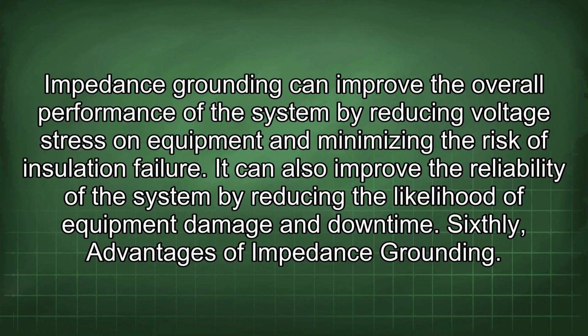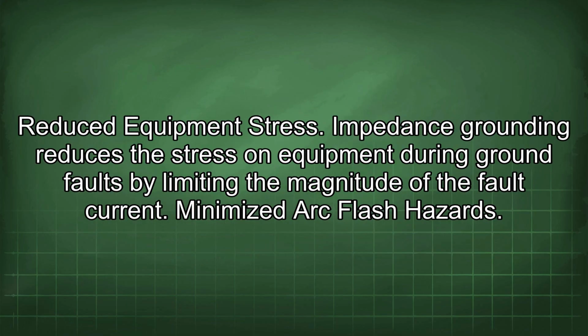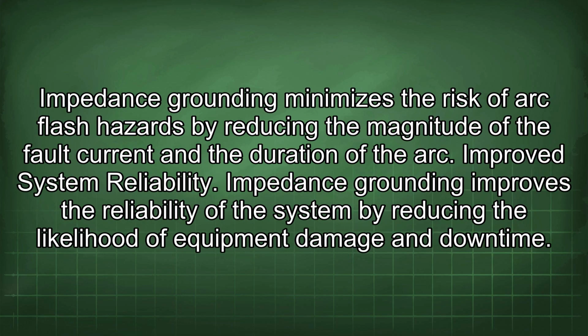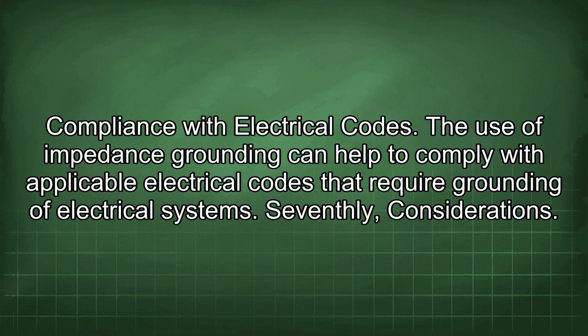Sixthly, advantages of impedance grounding. Reduced equipment stress. Impedance grounding reduces the stress on equipment during ground faults by limiting the magnitude of the fault current. Minimized arc flash hazards. Impedance grounding minimizes the risk of arc flash hazards by reducing the magnitude of the fault current and the duration of the arc. Improved system reliability. Impedance grounding improves the reliability of the system by reducing the likelihood of equipment damage and downtime. Compliance with electrical codes. The use of impedance grounding can help to comply with applicable electrical codes that require grounding of electrical systems.